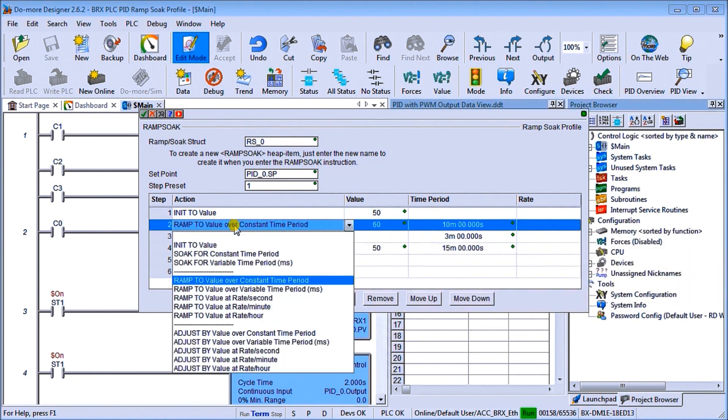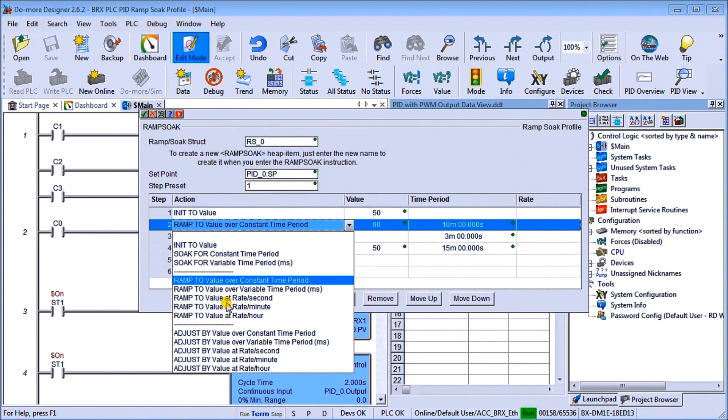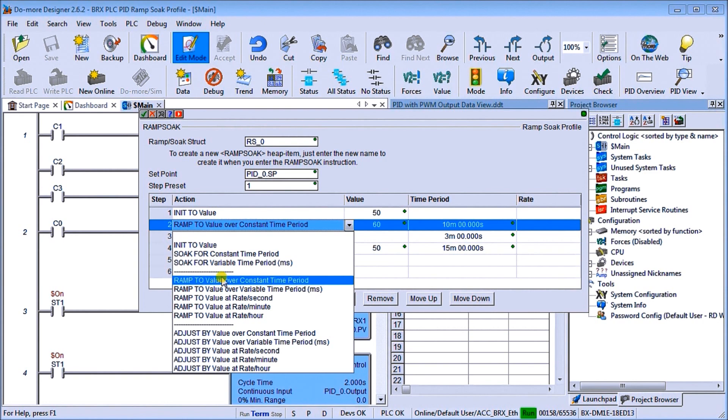Now, if we click any one of these, you'll see there's several different selections we can actually have. And we have right now, we have a ramp to value over constant time period. We have a variable time period milliseconds. Then we have a value to a rate per second. We have a rate per minute and a rate per hour. We also have adjust by value constant time period, variable or a rate per second rate per minute rate per hour. So there's a few things that we can actually do. So again, soak is when you maintain your present value and ramp is when you're either ramping up or ramping down the value.